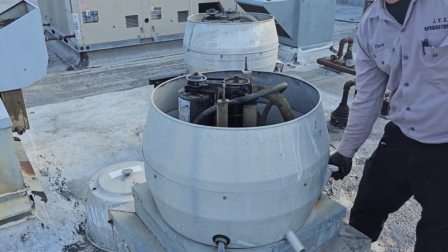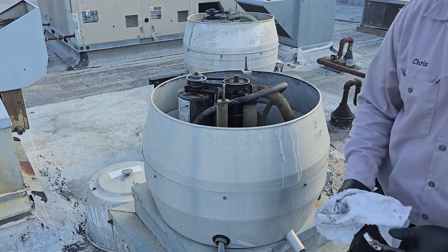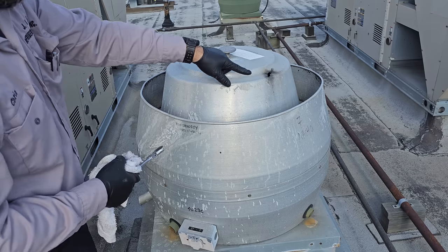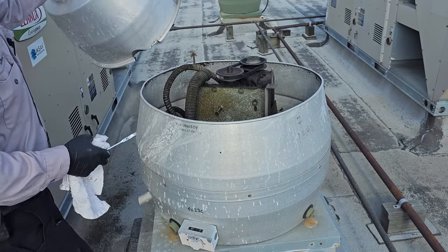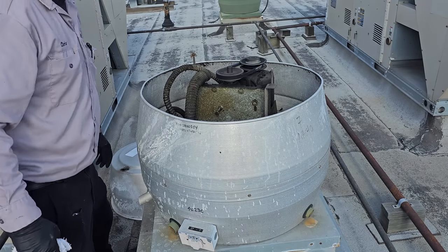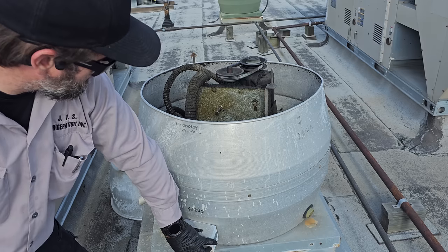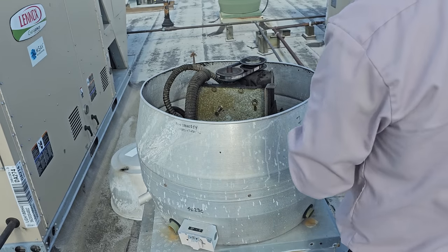Make sure they all go the same direction. Yep, going in the right direction. So we're good on that one. We got one more fan to go now. This one is vibrating to all hell. Yeah, this fan is toast. So we'll be quoting a couple new fans for them too.